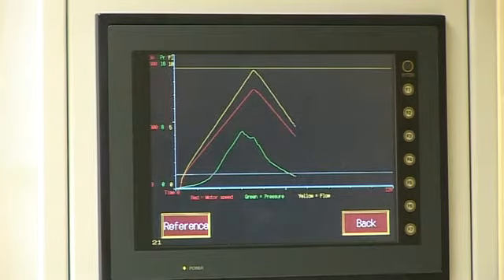Because the flow rate is directly proportional to the motor speed, the linearity of the Hydrocell pump approaches plus or minus 3% whether the motor is accelerating or decelerating across the full turndown range.